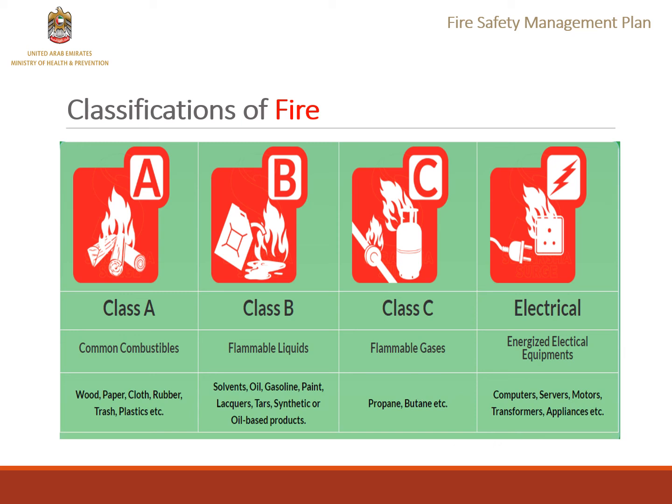So, carbon dioxide fire extinguisher is suitable for Class B and electrical related fires. If you go to your nearest fire extinguisher, you'll be able to see these signs easily. And for the dry powder, it can be used on Class A, B, C, and electrical as well. So it's more versatile than carbon dioxide. So again, carbon dioxide is used for Class B and electrical. Dry powder is used for Class A, B, C, and electrical.